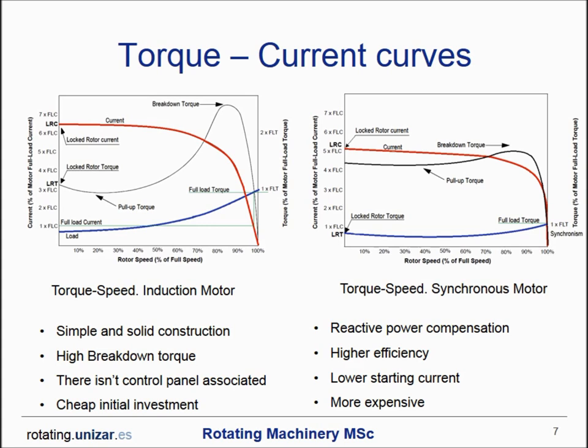On the other hand, synchronous motors, though more costly than induction motors, are preferred in many cases — especially as motor rating increases. The main reasons for selecting a synchronous motor are: reactive power compensation to adjust the plant's total power factor and avoid utility penalties associated with low power factor; higher efficiency, since exciting the rotor with DC current avoids much of the associated losses; and high starting torque with low starting current, resulting in less impact on the electrical grid.